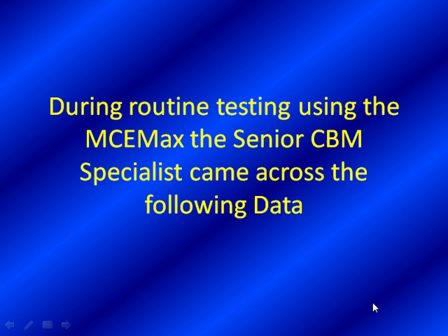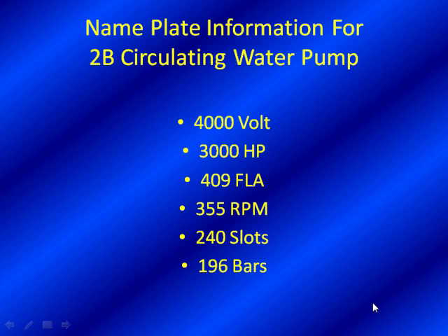So here we go, Noah. During routine testing using the MCEMax, the senior CBM specialist came across the following data. Let's take a look at the motor first. We have a 4,000 volt, 3,000 horsepower, 409 full-load amps, 355 RPM, and what we always like to tell our customers is look at this number: 240 slots and 196 bars. That's not normal information on the nameplate - the older the motor, the less likely it is to be there. It's good that the specialist got this number into his database, probably from the motor shop or the original equipment manufacturer.